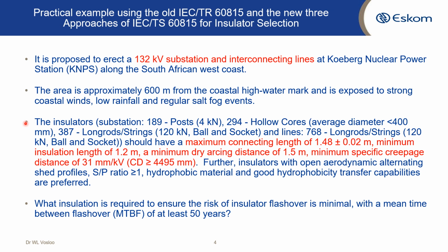We would like open aerodynamic alternating sheds, S over P ratio of greater than 1, and hydrophobicity transfer capabilities. And then obviously we would like to include the new statistical methods as required by approach 2 of the new 815.